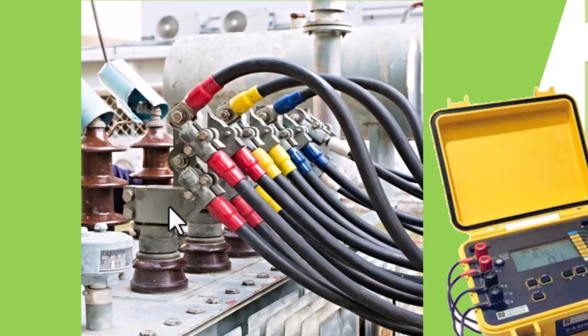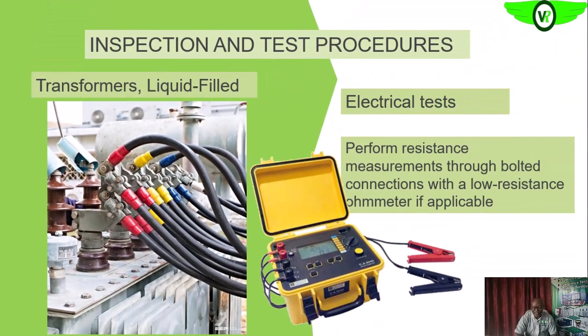Whether this could be the input or output. Okay, this is the output of the transformer. So remember, we want as low as possible resistance between this lug and the terminal to which it is connected. That is what we are actually testing, whether this lug is making proper connection with the terminal. As the resistance is going up, we know that can cause problems, because that can be a potential hotspot during operations and thus a point for potential failure, apart from the fact that it can reduce the efficiency of the equipment. So we want to test the resistances between this lug and the terminal to which it is connected. We can do it for all the lugs that are connected to that particular terminal.